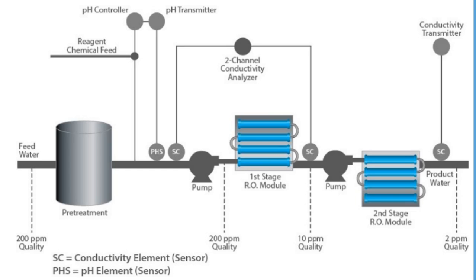It's important to note that preliminary water purification includes filtration, clarification, and softening prior to RO applications. The water flows through a two-pass RO system and a demineralization option for further purification. The RO system produces one purified water stream called permeate and a second stream referred to as concentrate, brine, or reject. Feed water enters the machine at a fairly low pressure and flows through pre-filters to remove suspended particles such as silt. A pre-filter is typically a replaceable cartridge type, which provides a cost-effective method for keeping the membrane clean. Typical life expectancy for these membranes is approximately 3 years.